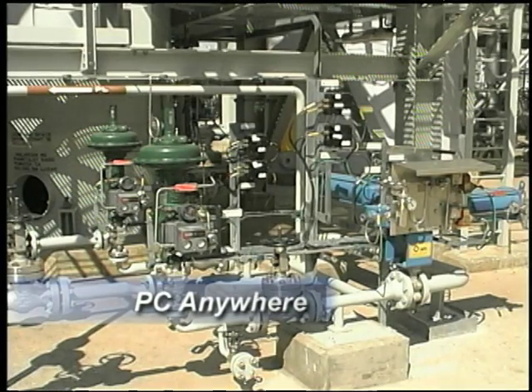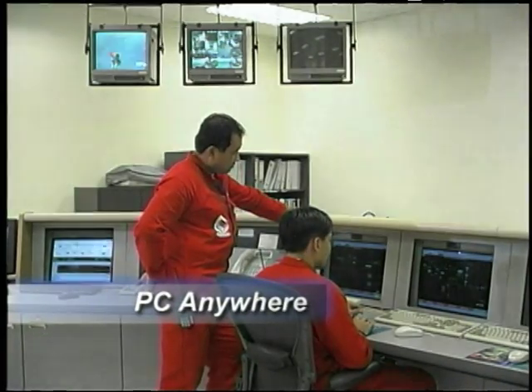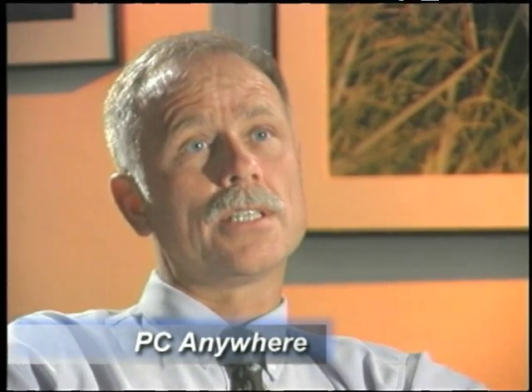With the system's remote diagnostics and control features, Malampaya project stakeholders can monitor the process anytime, anywhere. During commissioning, a link with Austin using PC Anywhere access to the system helped a lot with troubleshooting. The benefit of remote monitoring is cost — experts in their own office environment can review incoming information, analyze it, and provide feedback. Remote access has also been tied into maintenance contracts, making suppliers responsible for the condition of their own equipment even without representatives on the platform.